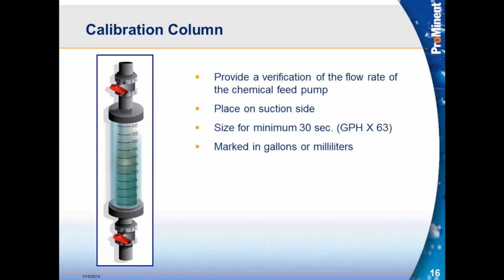Now with our pumps with a digital display on them, the Gamma L, the Delta, and the Sigma control versions, all of those have calibration features to them. And what I mean by that is we can do a drawdown test. We're not keeping track of the time. The pump is counting the number of strokes, but we put in the volume that it drew down in that number of strokes, and it's going to do simple math to calculate what the volume for each individual stroke is, or per stroke. So once it knows the volume per stroke, it can extrapolate out if it knows how many strokes per hour it's going to do, and it can actually display the flow rate in either gallons per hour or liters per hour, depending on how we've calibrated.